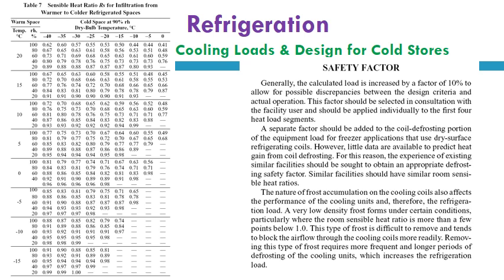which is 24 divided by 18 hours. For example, if we have 6 hours for the defrosting process, the additional safety factor should consider the actual time of operating without frosting, relative to the total of 24 hours, since the load is calculated based on 24 hours as mentioned in the previous slides during the transmission load and the product load, and the time to cool down the product.